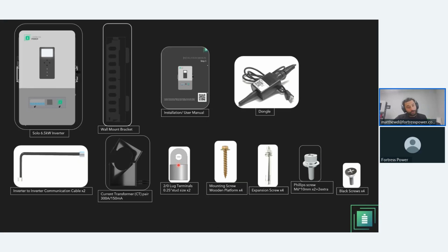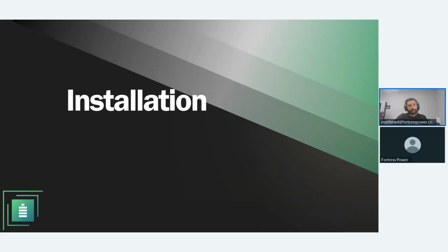It comes already with 2/0 lug terminals, so all you need to bring is really your crimper rated for 2/0, your mounting screws, expansion screws, and then Phillips screws and some black screws. This is just basically to lock the inverter in place when you're installing the wall mounting bracket. And then your battery screw terminals, which are already connected into the battery port. Okay, installation.